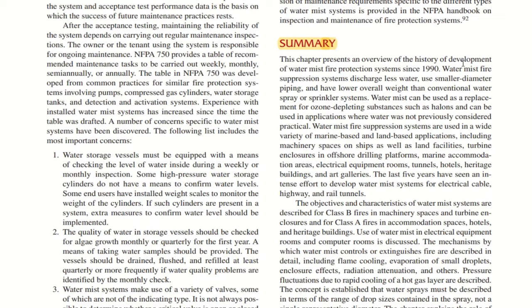This chapter presents an overview of the history of development of water mist fire suppression systems since 1990. Water mist fire suppression systems discharge less water, use smaller diameter piping and have lower overall weight than conventional water spray or sprinkler systems. Water mist can be used as a replacement for ozone depleting substances such as halons and can be used in applications where water was not previously considered practical. Water mist fire suppression systems are used in a wide variety of marine based and land based applications, including machinery spaces on ships as well as land facilities, turbine enclosures in offshore drilling platforms, marine accommodation areas, electrical equipment rooms, tunnels, hotels, heritage buildings and art galleries.